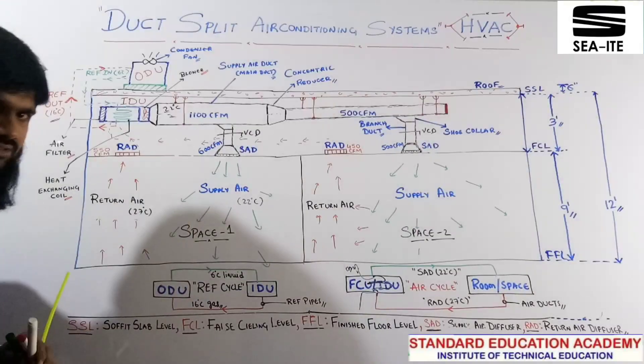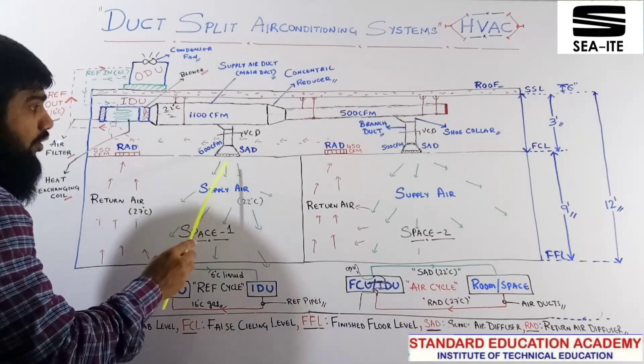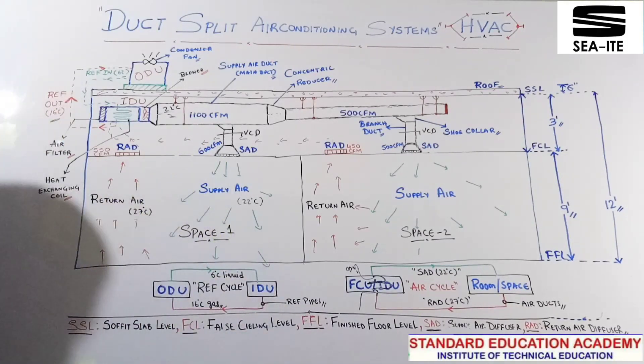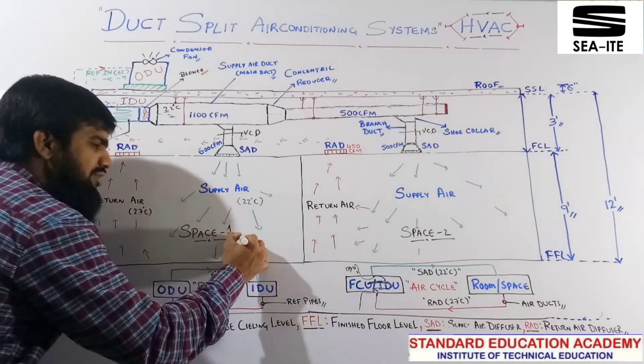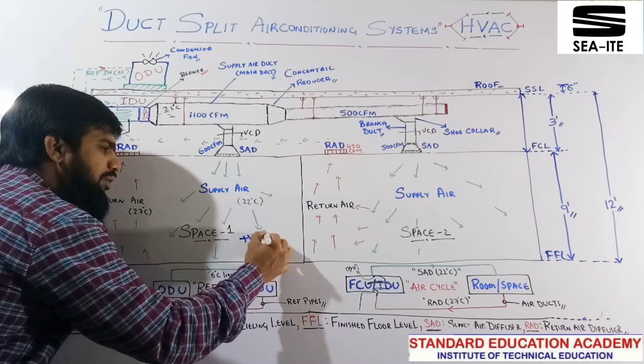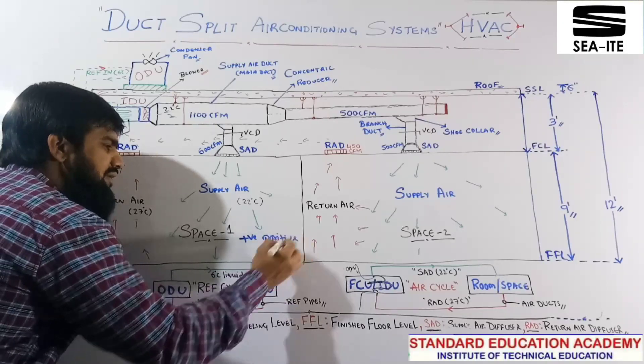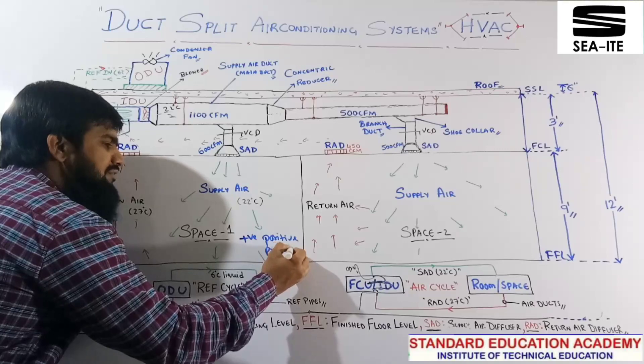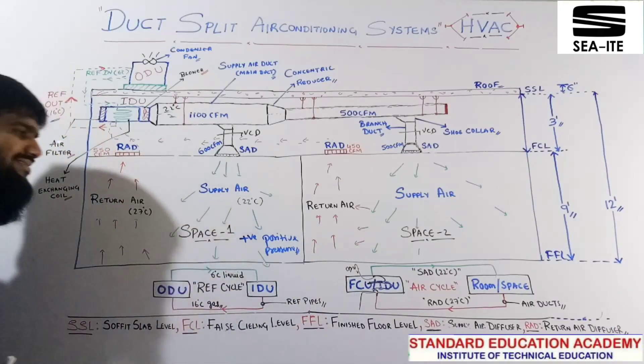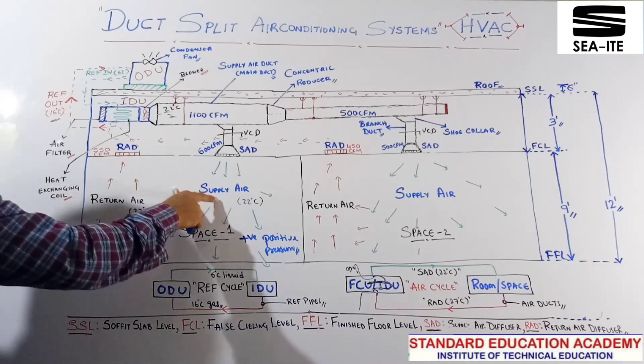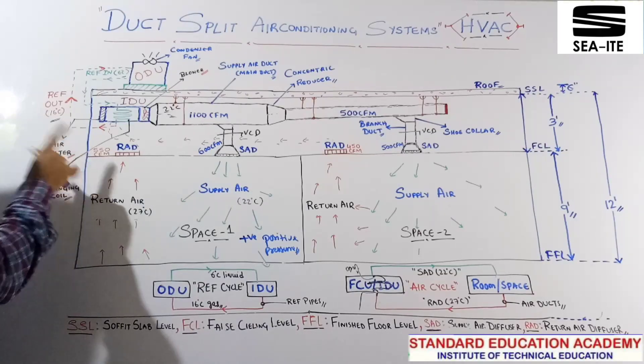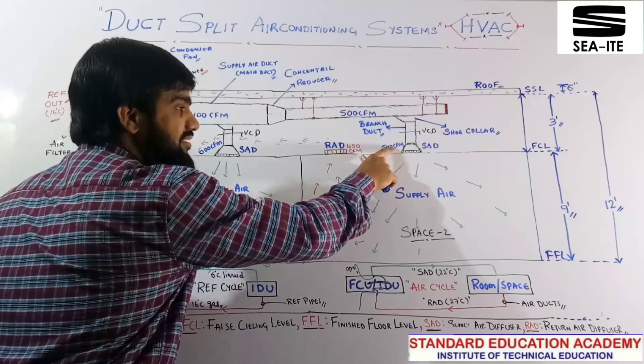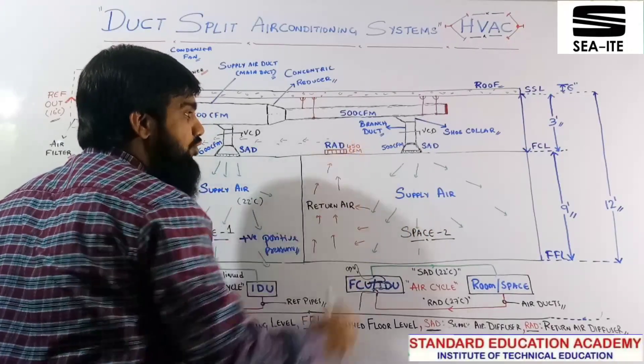One important point: I am supplying 600 CFM but I am taking back only 550 CFM. I am not taking back the total 600 CFM. Why? Because in working spaces we have to maintain positive pressure. That is the reason why we take back less air compared with supply. Supply CFM 600, return CFM 550. Similarly for the other space, supply CFM 500, return CFM 450.